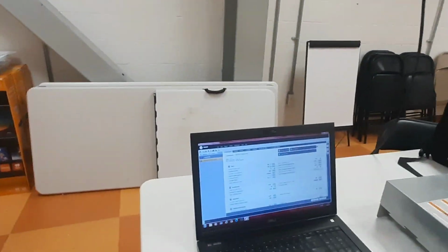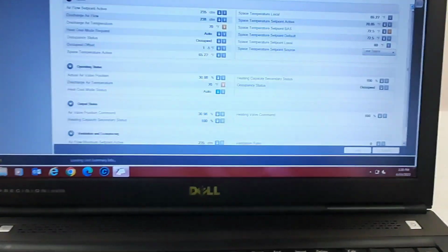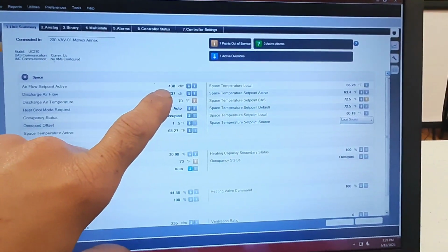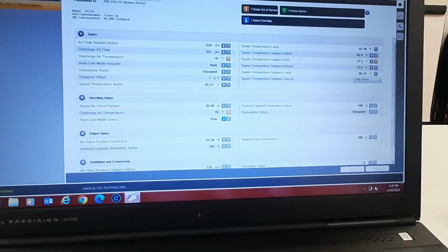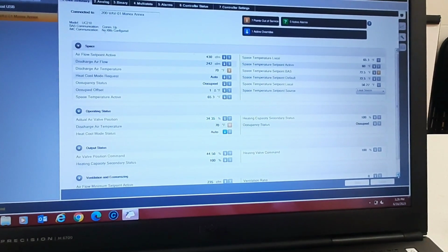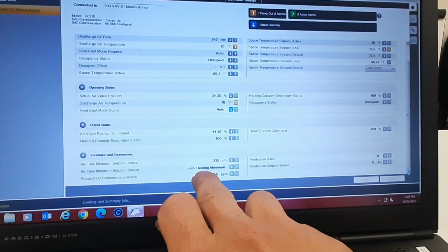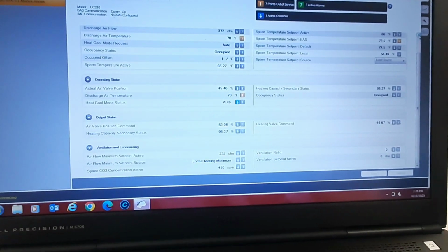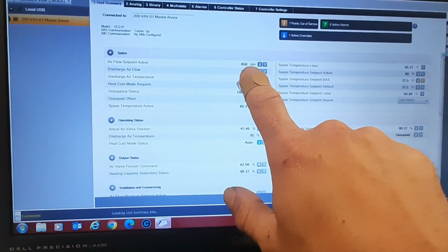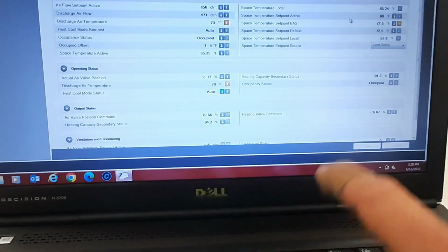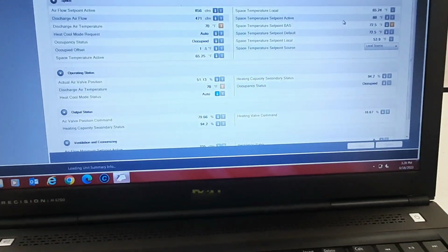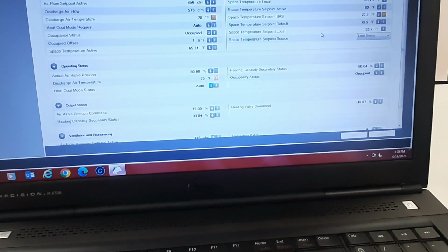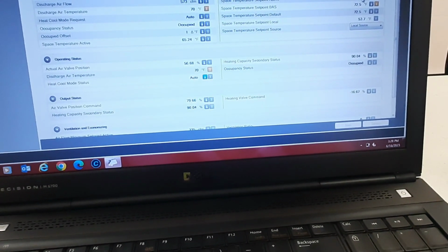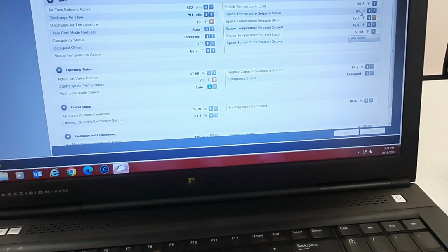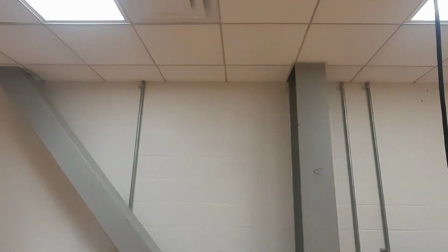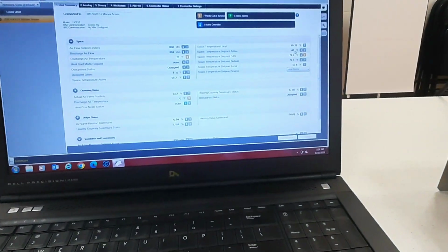So that's a plus. If we crank it down, we should see that airflow set point CFM go up. And then, because I'm going to be on, it hadn't changed here yet, local heating minimum, it should go to cooling minimum, and that's why my set point active went up. Just hadn't changed over there yet. And then my actual heating valve is going to drop down because it's calling for cooling now. I need to go back in and change my cooling low set point to, I don't know, 65 or something. But I can hear the airflow again. I like it. I don't know why this wanted to be such a pain.